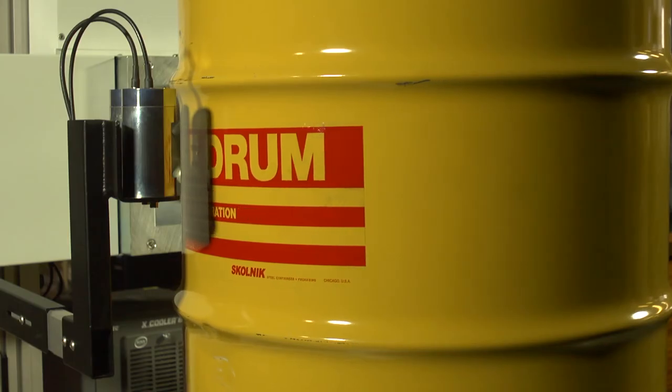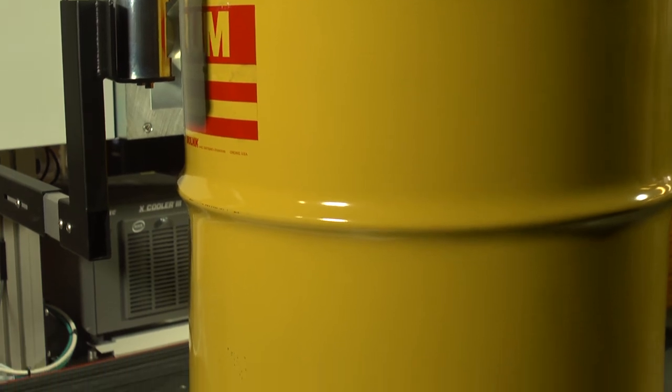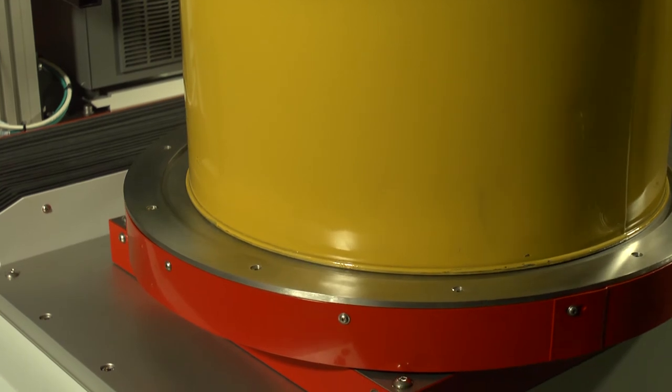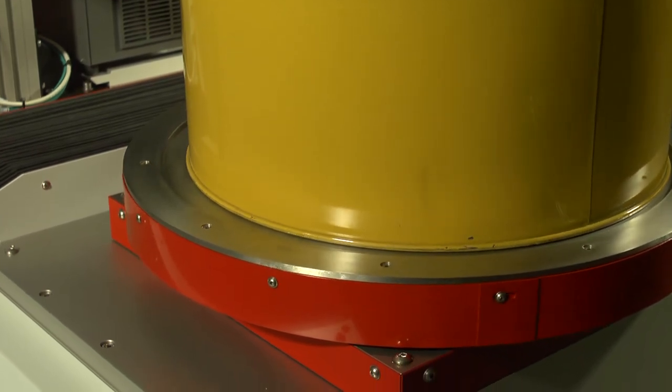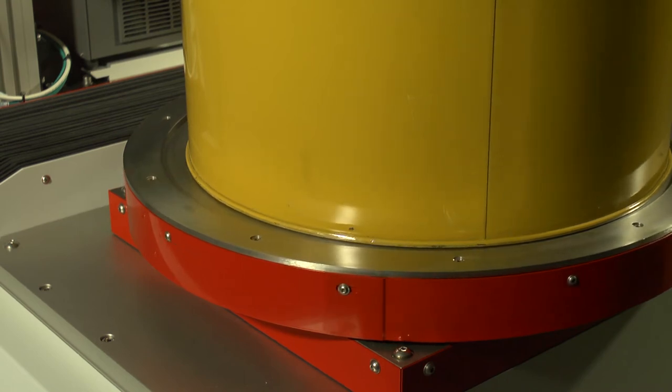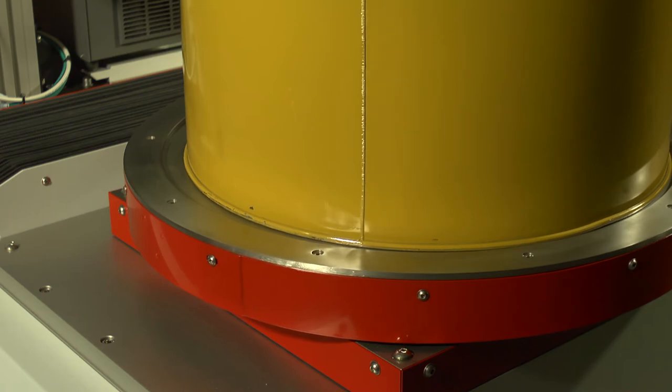Waste drums, which are typically 200 litres or 55 US gallons, or alternatively 400 litres in volume, are placed on the drum rotation platform. The drum rotation platform incorporates a load cell to measure the drum weight, from which the density of the material in the drum or the drum matrix can be determined.